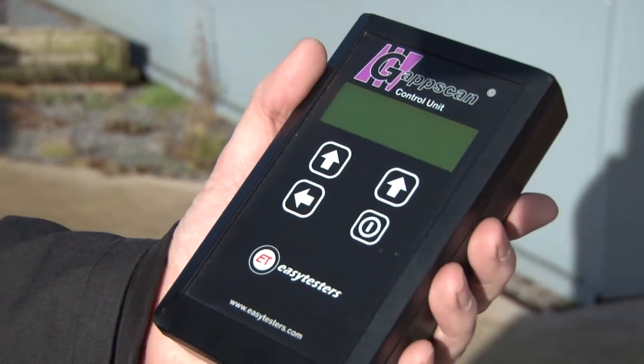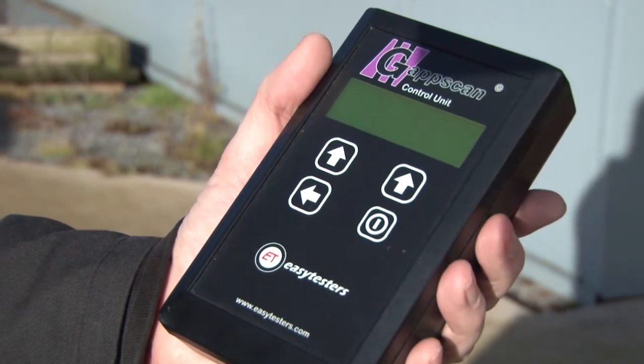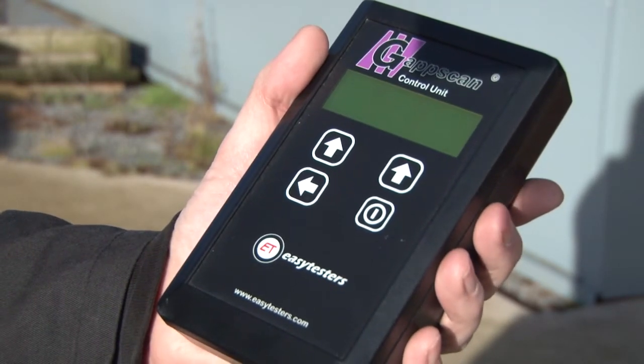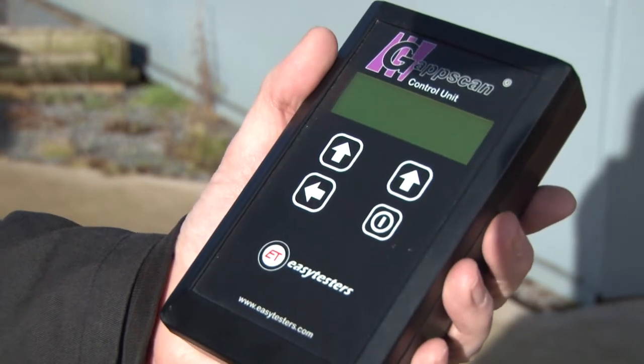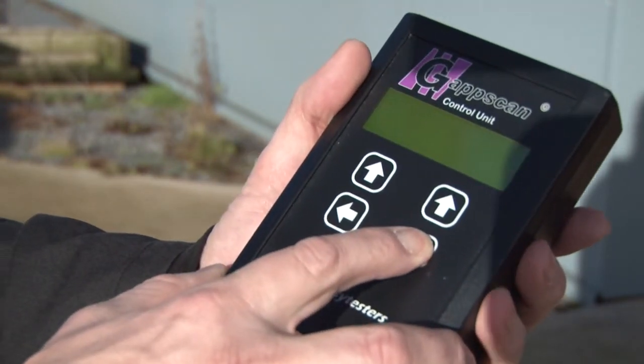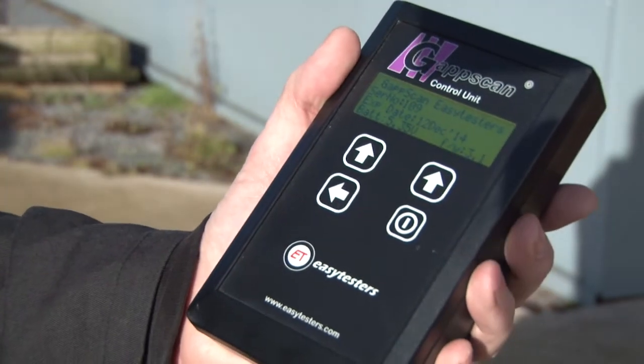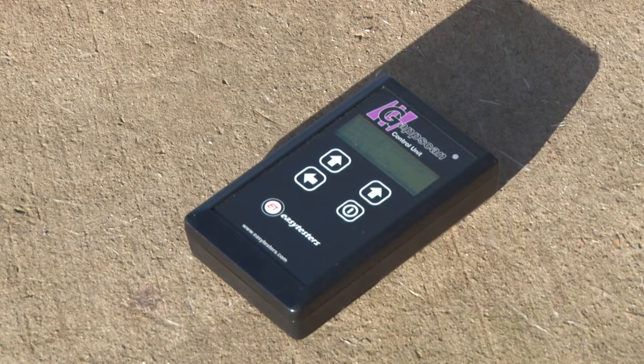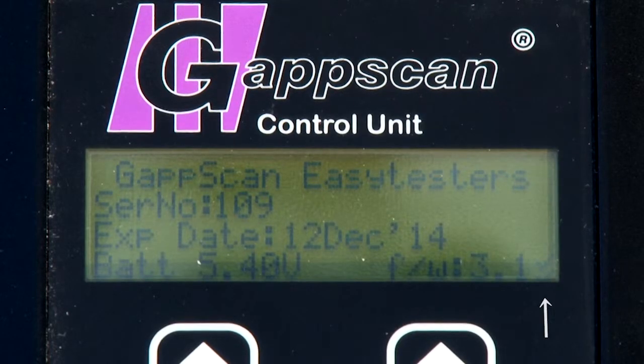You need to make sure that you are in a good position with the control unit in order to get a GPS signal, as the test will not commence without GPS. You can go outside to get this fix. Switch on the unit. Place the unit face up. In the bottom right side of the screen, you will see 2 ticks appear when GPS has been fixed. This may drop to 1 tick when inside, but the control unit will still operate with 1 tick.